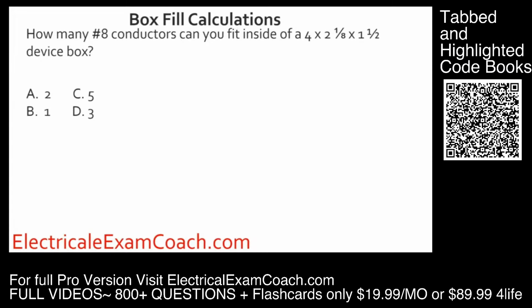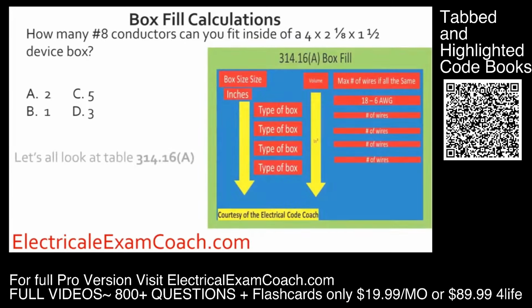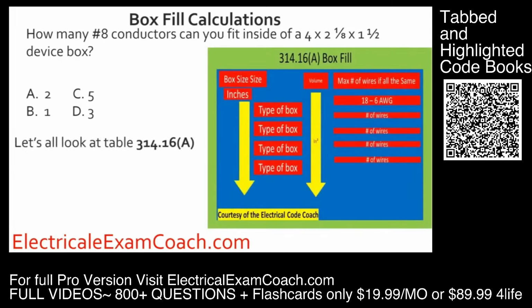How many number 8 conductors can you fit inside of a 4 by 2 1/8 by 1.5 device box? We head to 314.16a. We're going to find our gauge wire. Then we're going to come over and find our type of box and size, make sure we do everything correctly, and we're going to find that it holds 3.